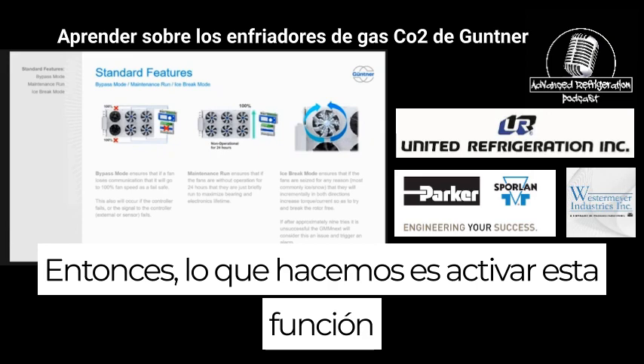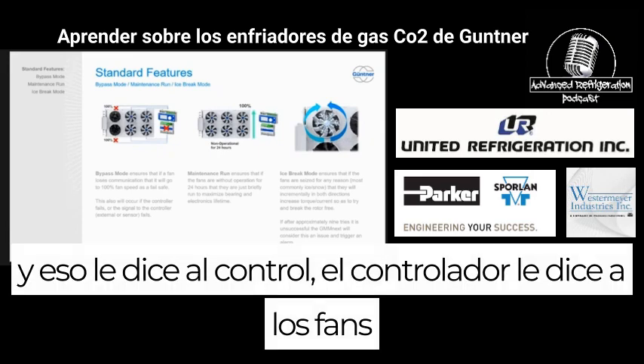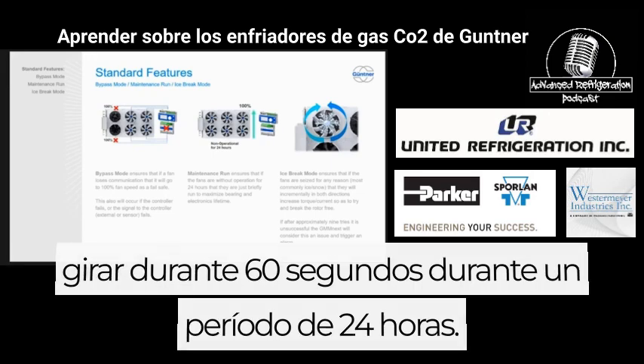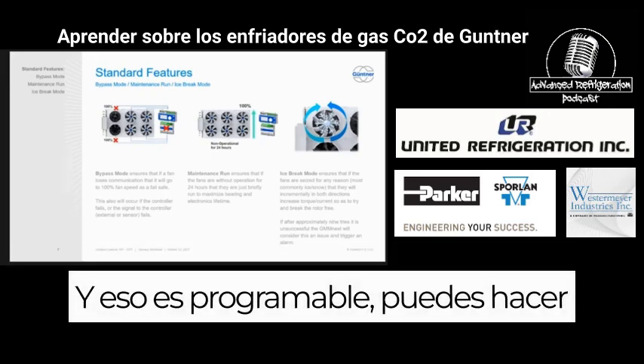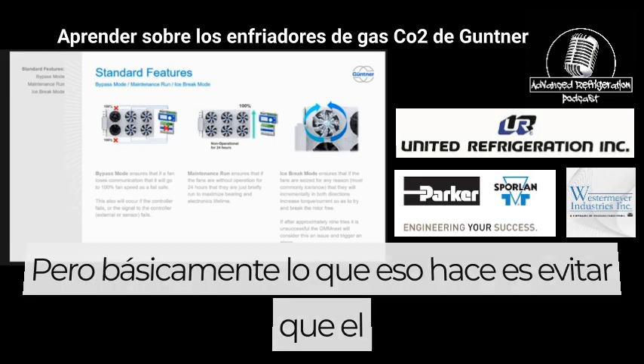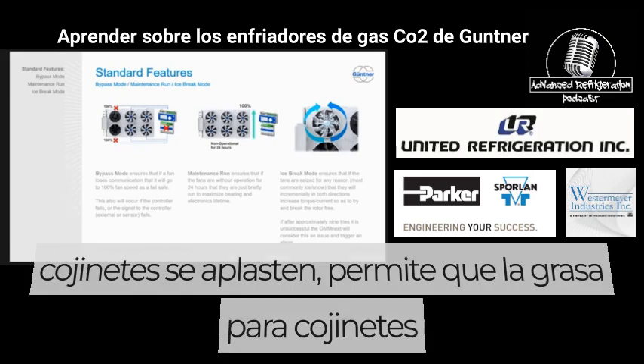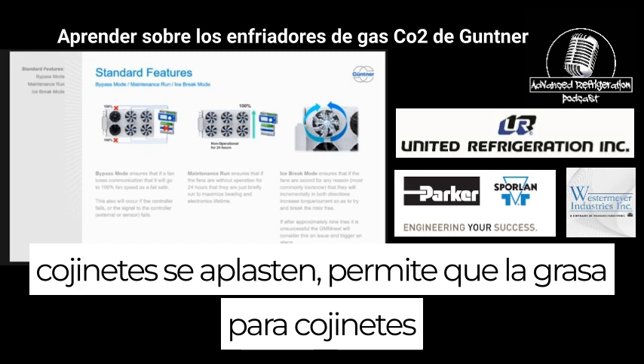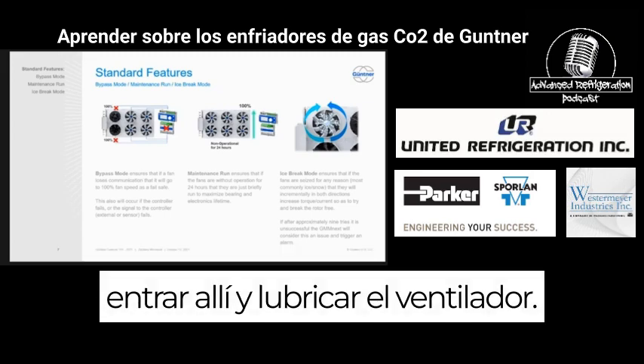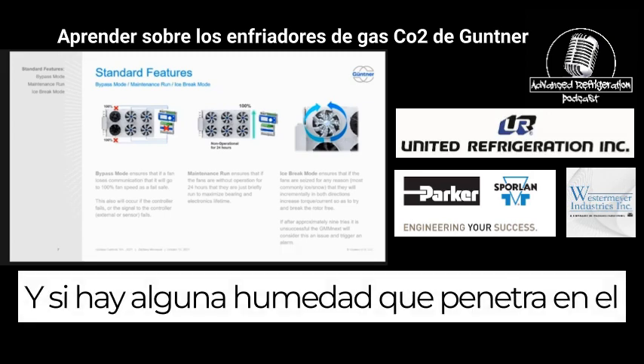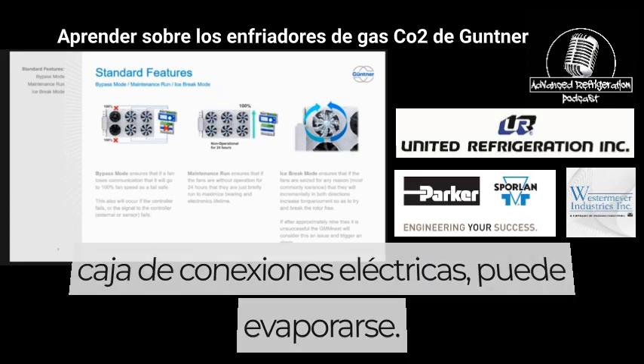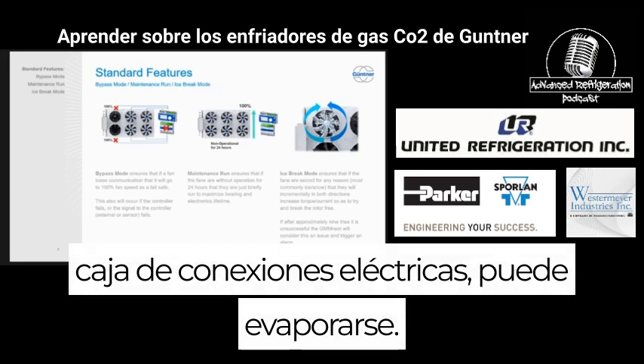So what we do is we turn this feature on. And that tells the controller to tell the fans to spin for 60 seconds during a 24-hour period. And that's programmable. You can make it run a little bit longer. But basically what that does is prevent the bearings from flattening, allow the bearing grease to get in there and lubricate the fan. And if any moisture penetrates the electrical terminal box, it can evaporate that away.